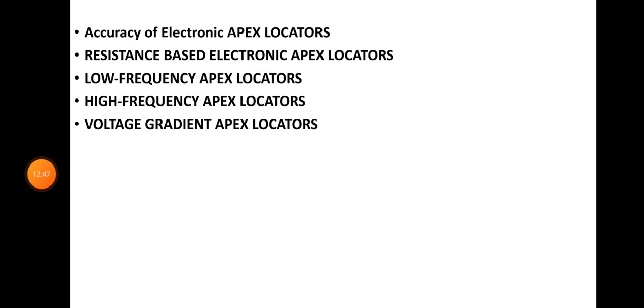Now let's talk about the voltage gradient apex locators. Custer and subsequently Sunada relied on a constant resistance value of 6.5 kilo ohms between the canal and the periodontal membrane, and Yoshiyama used both monopolar and bipolar electrodes coated in lacquer with just the tip exposed.